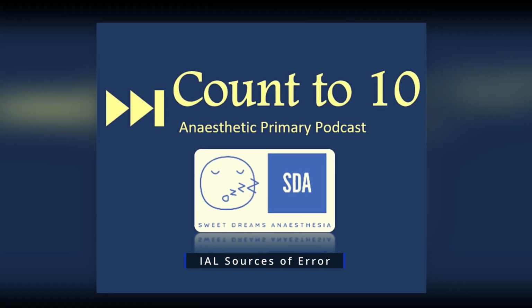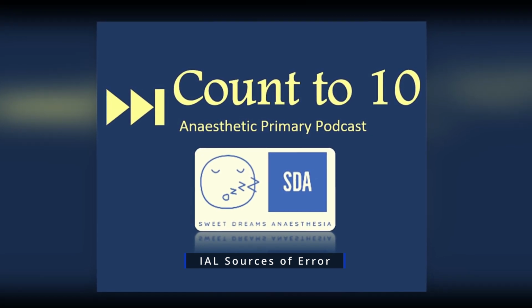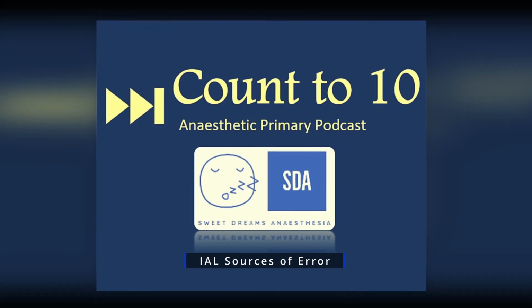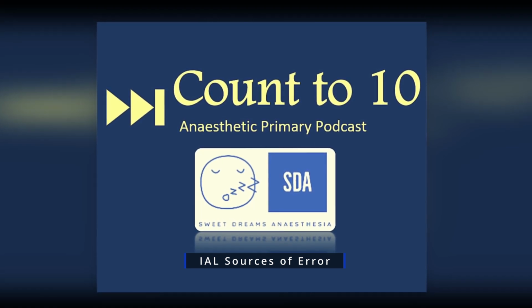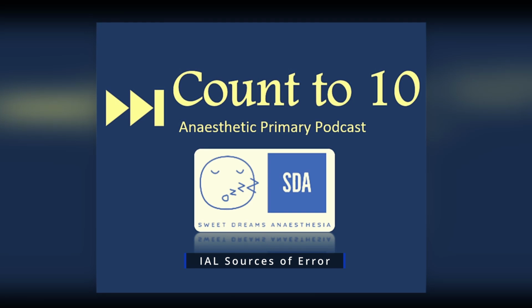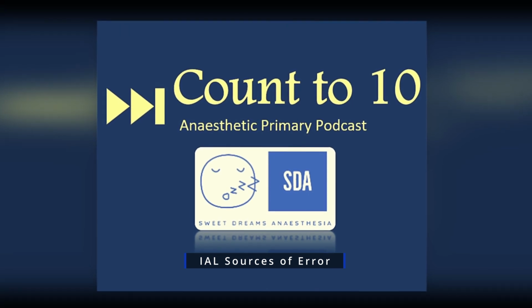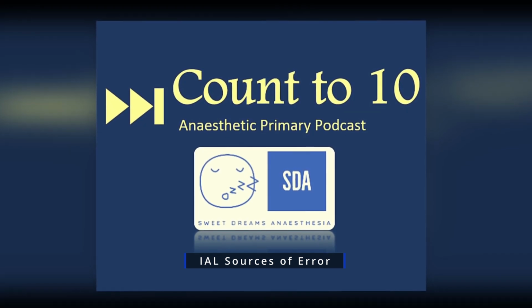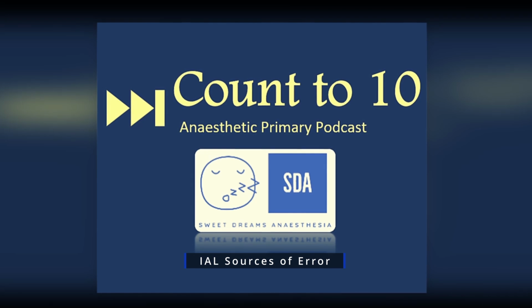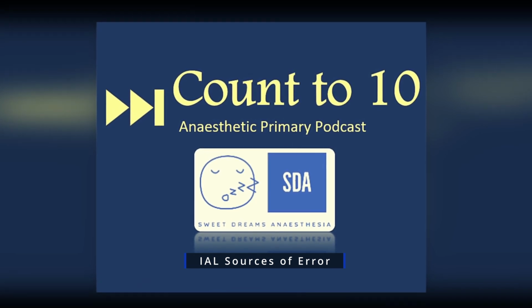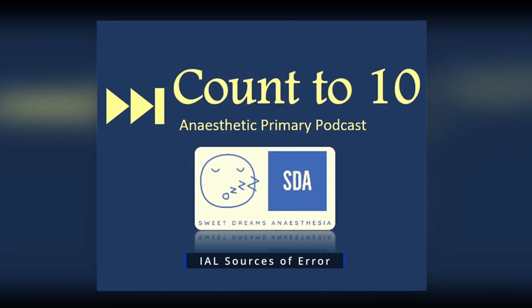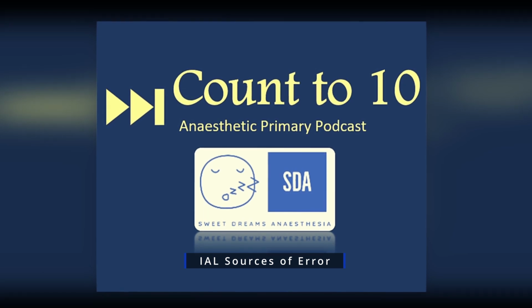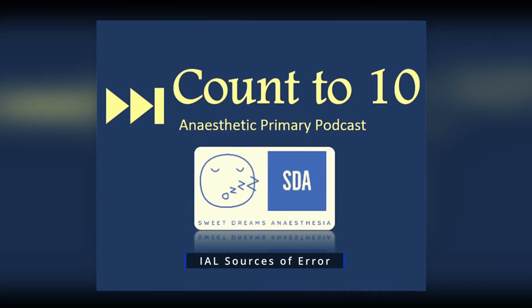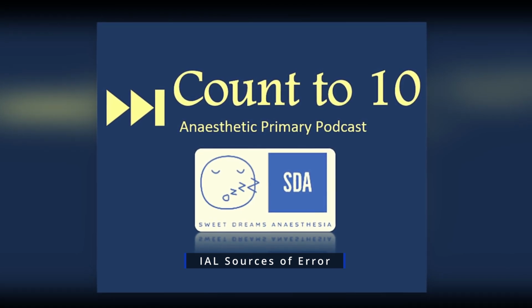The key thing to know with leveling is that a change in height can have a huge impact on the output of the measured blood pressure. Classically, we say a change in height of 10 centimeters equates to a change in pressure of 7.4 millimeters of mercury. So these are the 2 static errors, and they're pretty straightforward to understand. Now we get into the dynamic errors, and these are far more likely to be asked in both SAQs and Vivas. The 2 dynamic errors are resonance and damping.